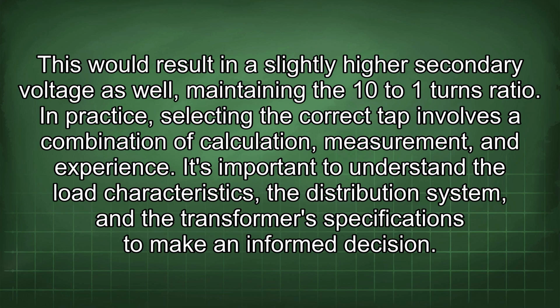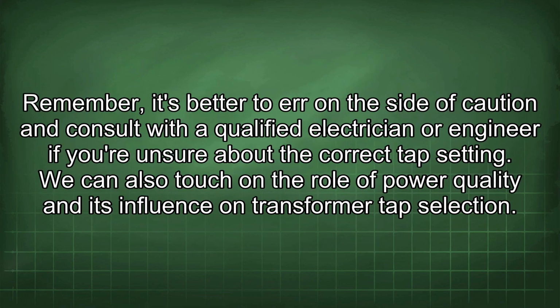In practice, selecting the correct tap involves a combination of calculation, measurement, and experience. It's important to understand the load characteristics, the distribution system, and the transformer specifications to make an informed decision. Remember, it's better to err on the side of caution and consult with a qualified electrician or engineer if you're unsure about the correct tap setting. We can also touch on the role of power quality and its influence on transformer tap selection.